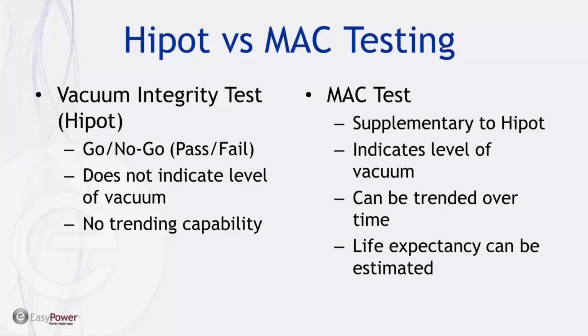And so we know the approximate point of failure with regard to pressure for these vacuum interrupters. So when that data point approaches this point of failure, then you have time to plan for replacement and plan to replace it before failure occurs. Not only that, over time, as more tests are done on the same vacuum interrupter, those data points can be trended, and extrapolated to give you an estimate of when that failure point would be way ahead of time.